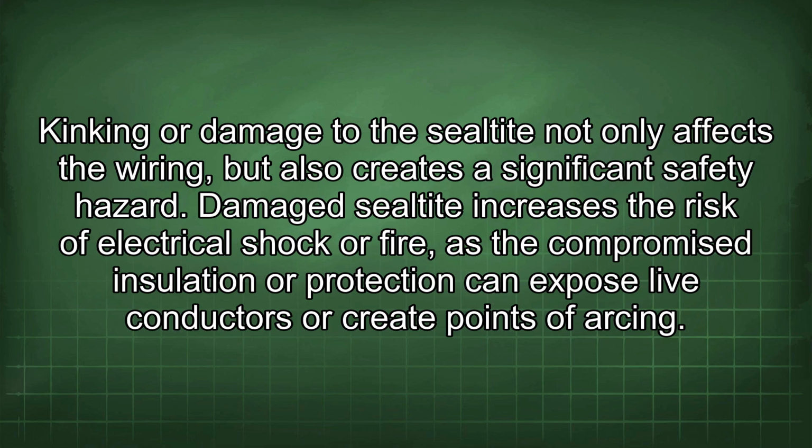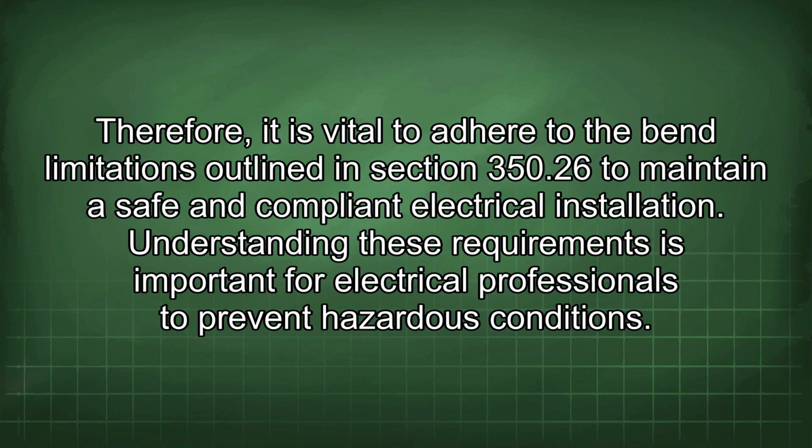Damaged Sealtite increases the risk of electrical shock or fire, as the compromised insulation or protection can expose live conductors or create points of arcing. Therefore, it is vital to adhere to the bend limitations outlined in Section 350.26 to maintain a safe and compliant electrical installation. Understanding these requirements is important for electrical professionals to prevent hazardous conditions.